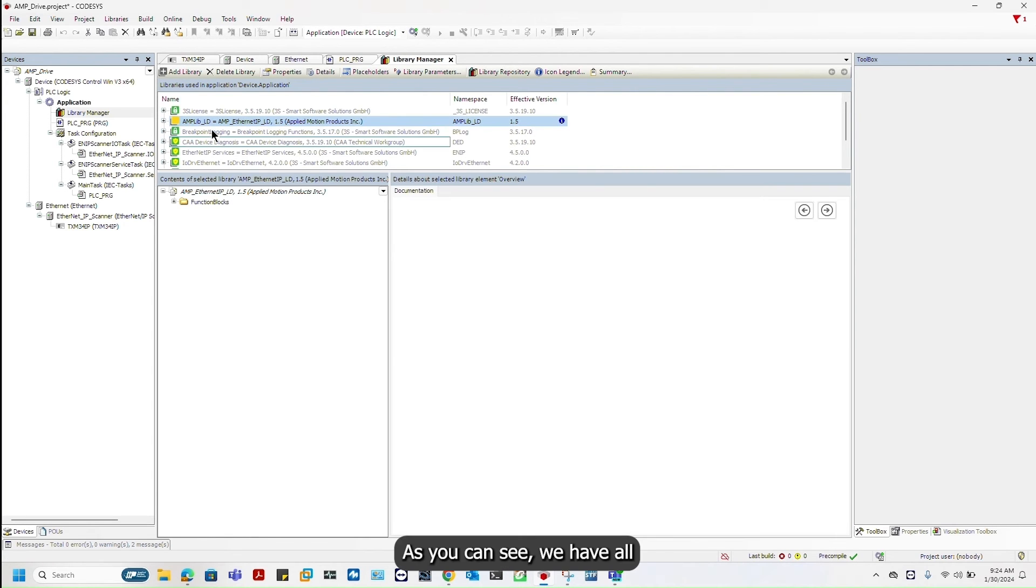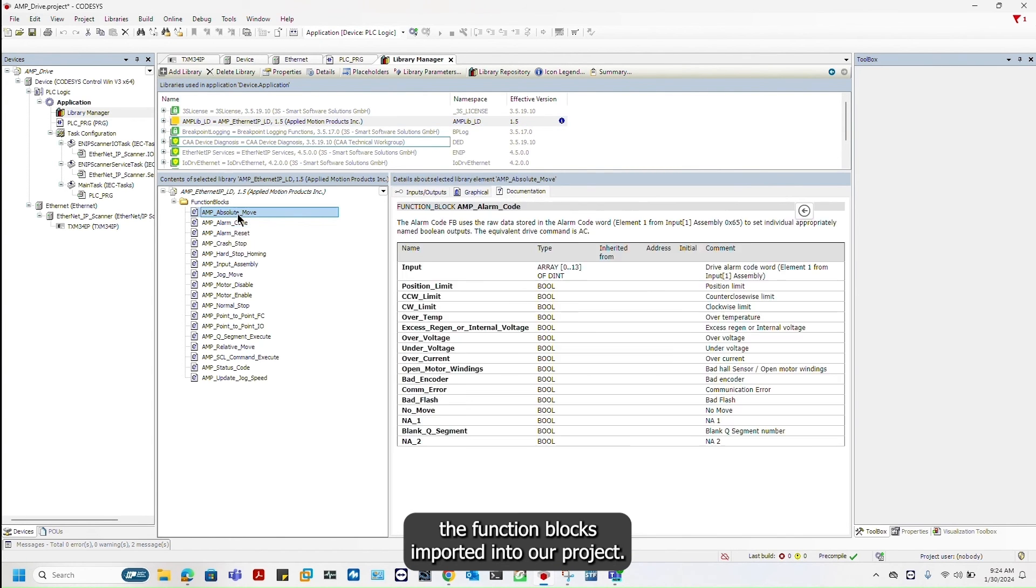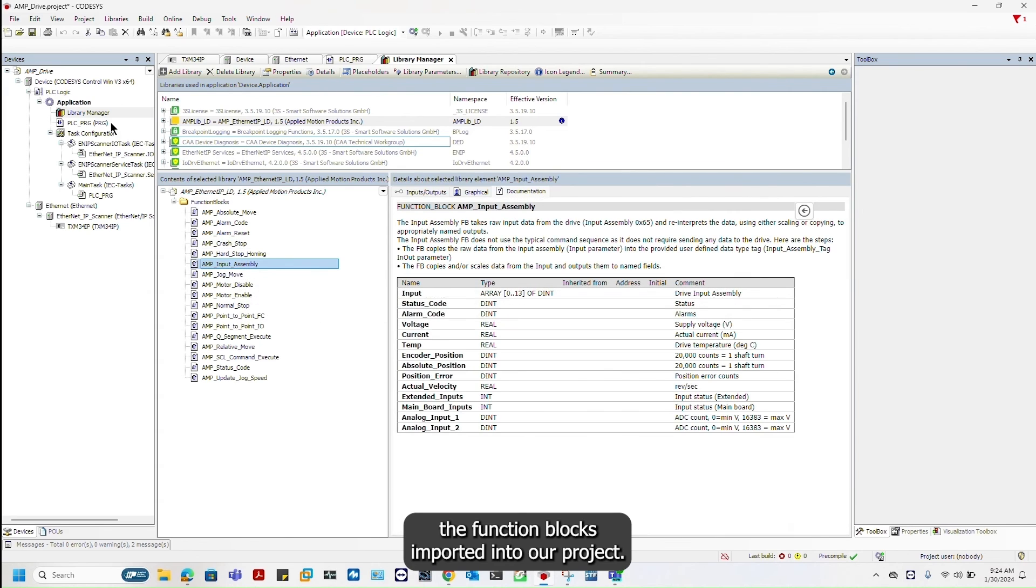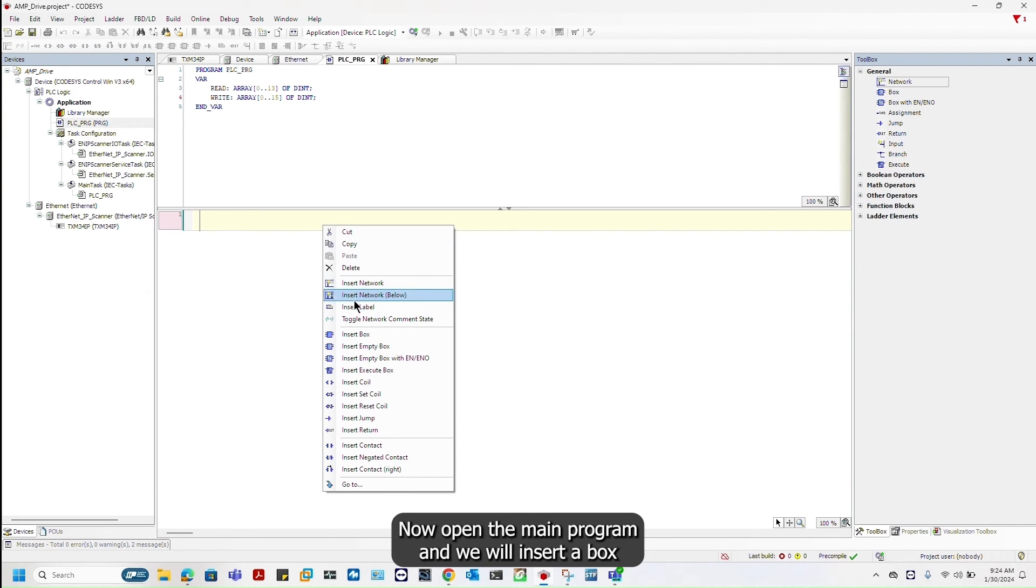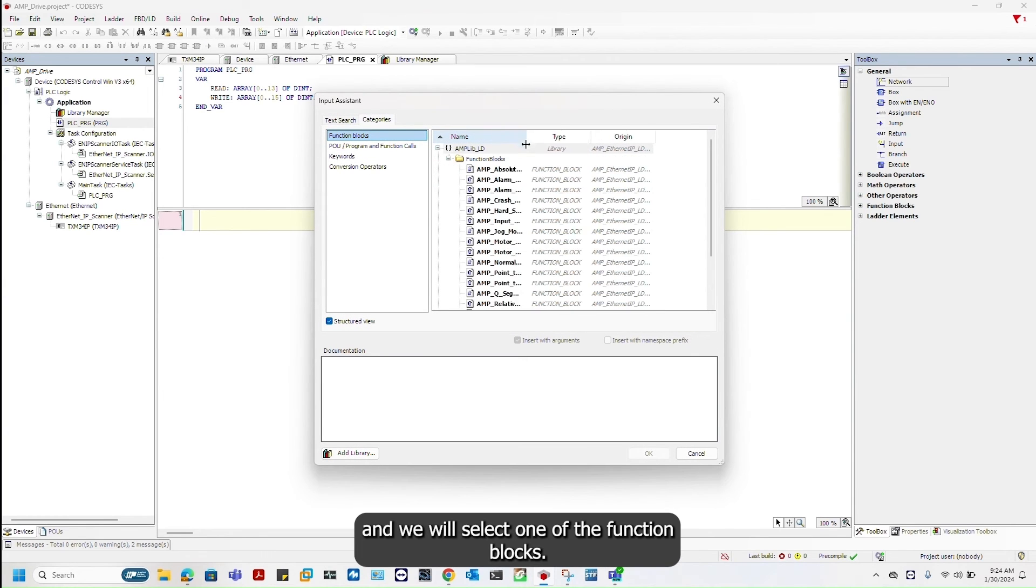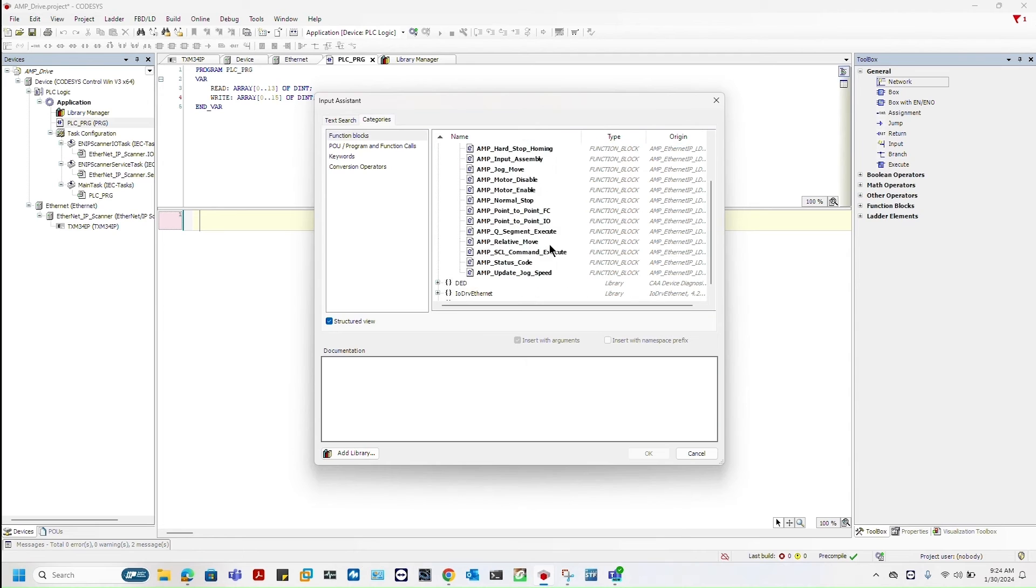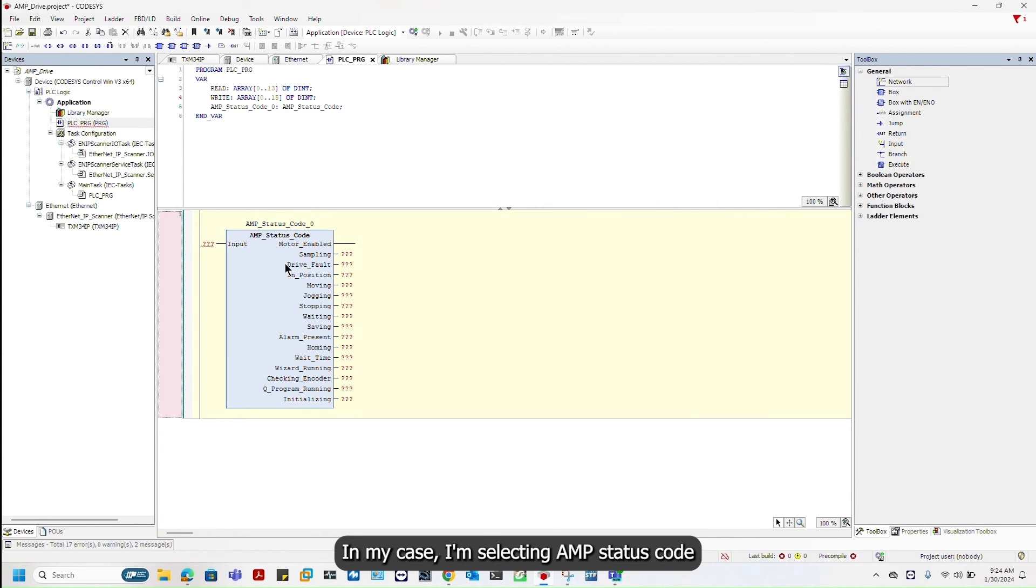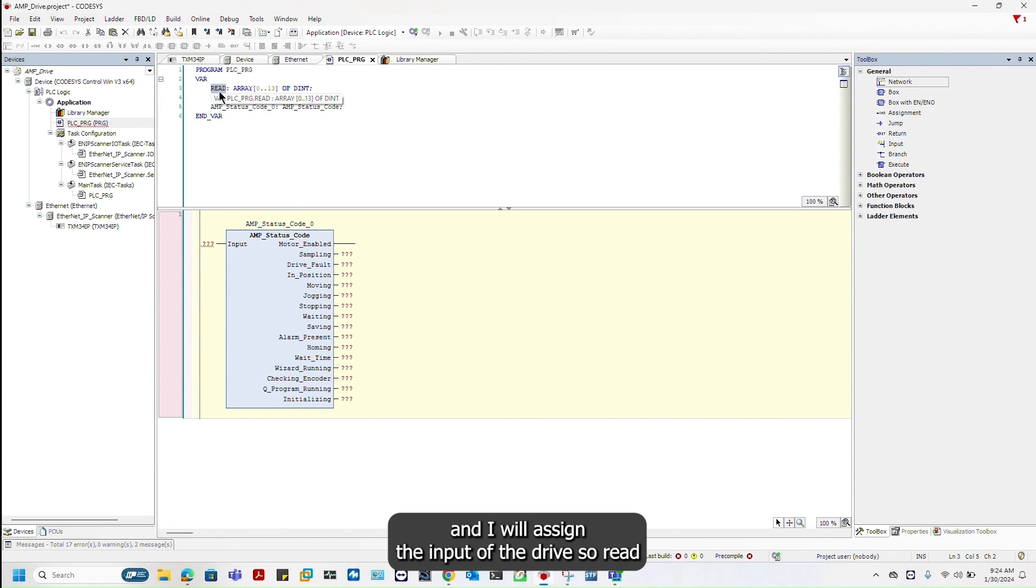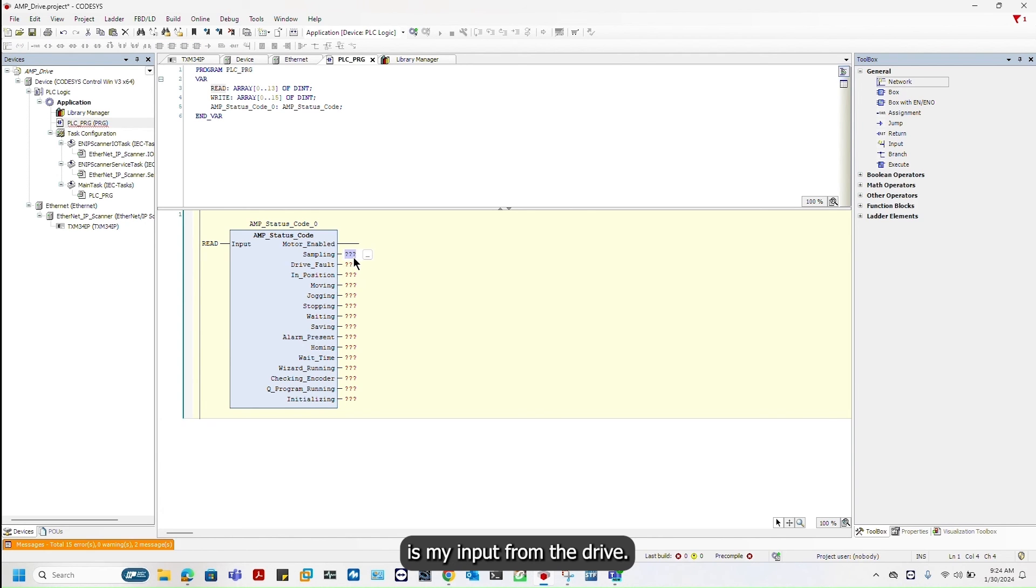As you can see we have all the function blocks imported into our project. Open the main program and we will insert a box and select one of the function blocks. In my case I'm selecting AMP status code and I will assign the input of the drive. Read is my input from the drive.